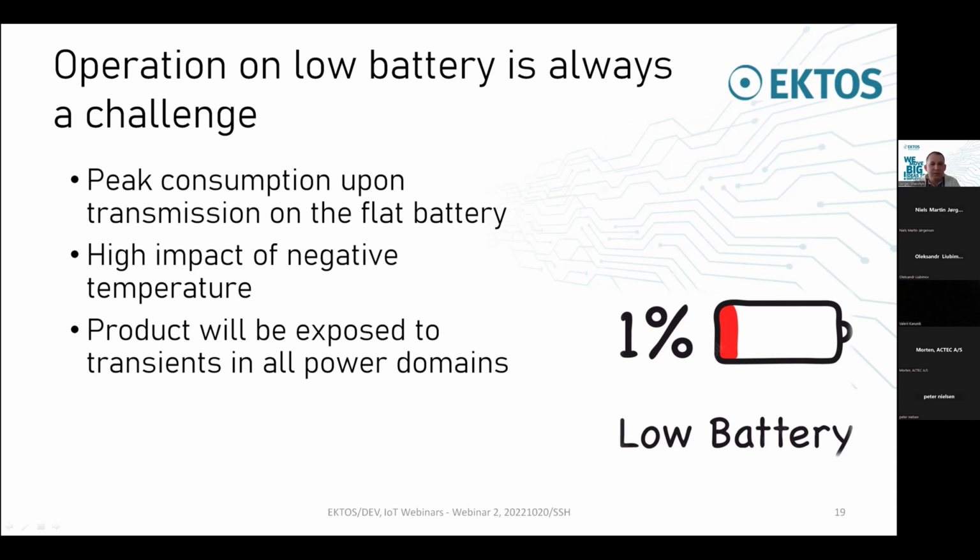And yeah, also the product will be exposed to transients in all power domains, meaning basically this low power or flat battery is abnormal operation for the product, and it shall be handled correctly. So the power supplies, or different power domains, shall be designed correspondingly.